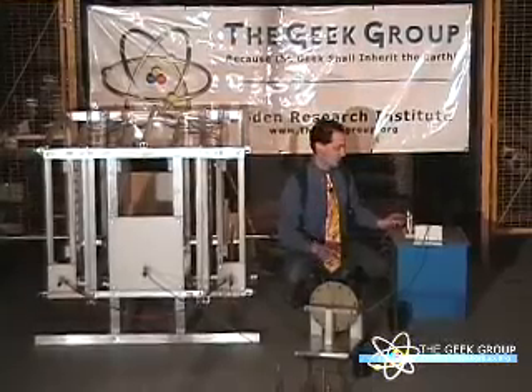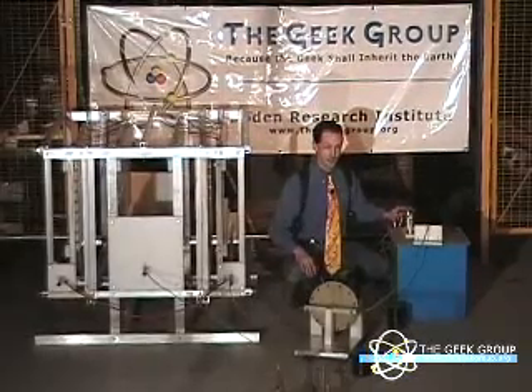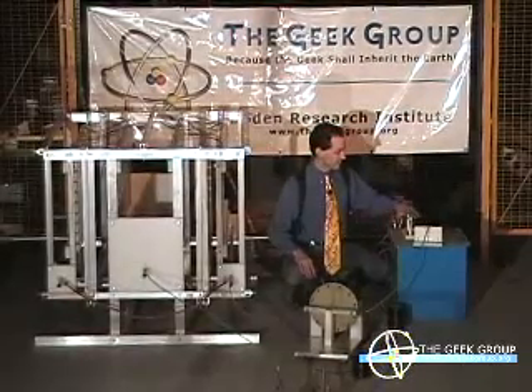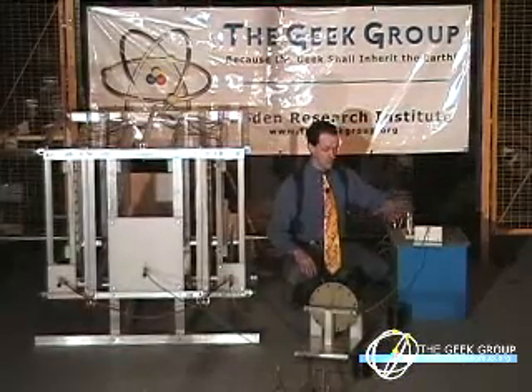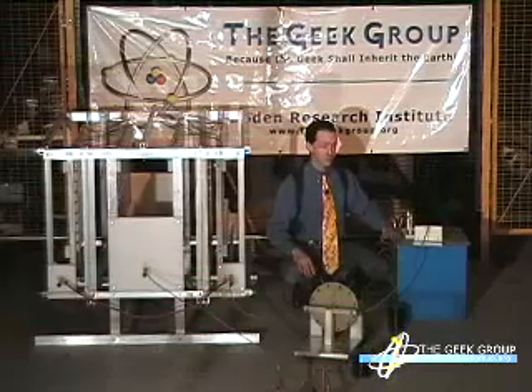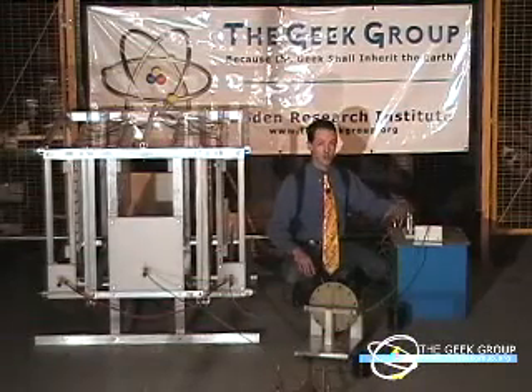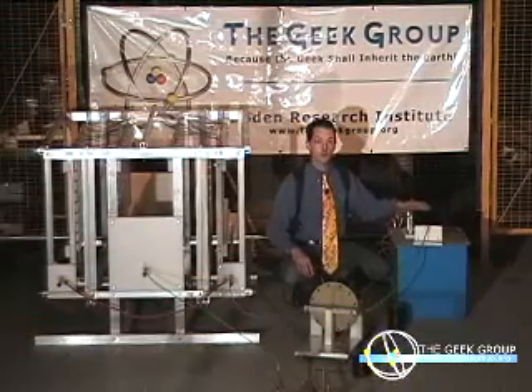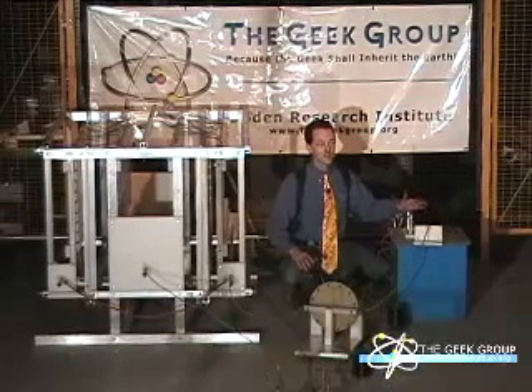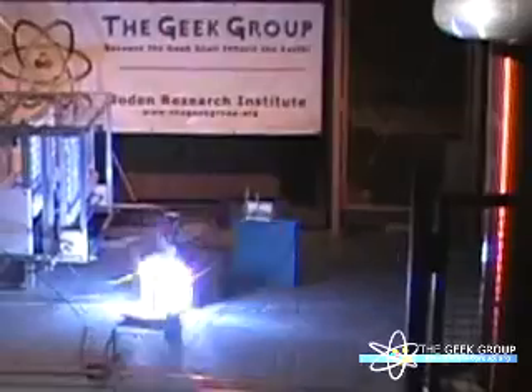To protect the transformer, we have a safety gap. Now, the purpose of the safety gap is that if any voltage across the system exceeds what the transformer is rated for, this grounds everything out. It's a voltage-controlled switch. At about 16,000 volts, this fires and dumps everything to ground. This protects the transformer, capacitors, and the entire rest of the system.